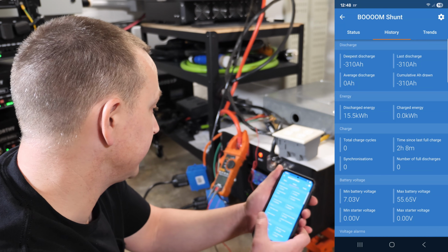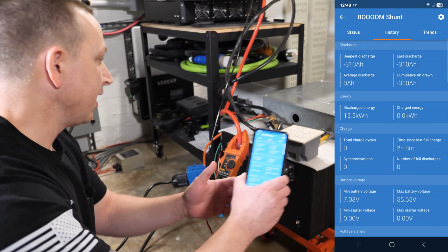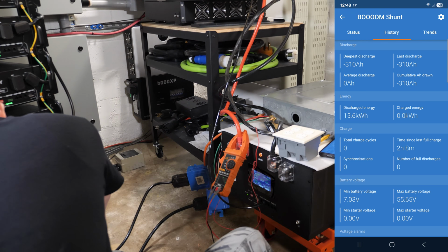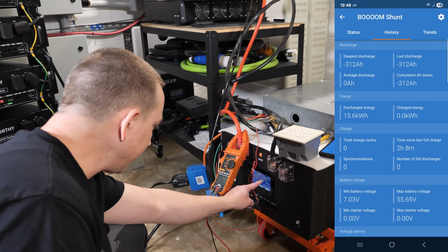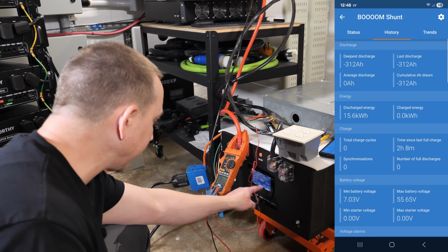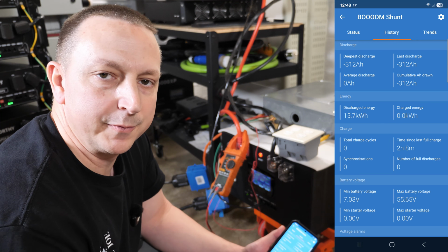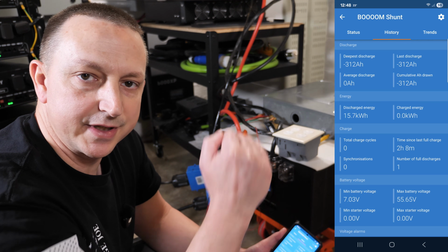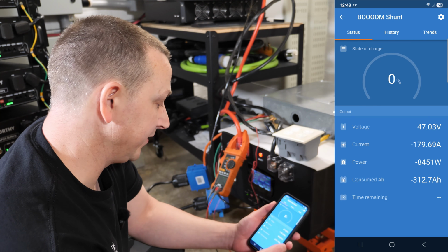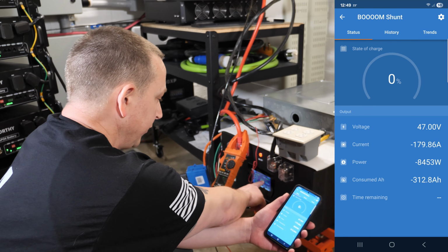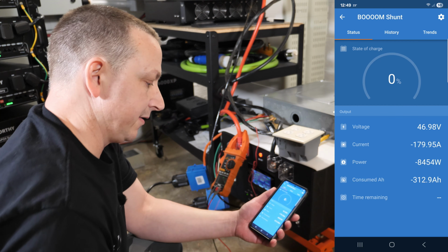I'm going to leave it on here so we can see it. I'm gonna have to adjust the amperage down again. So I dropped it down, we're at 187 right now, and that should give me a little room, because when the voltage goes down the amperage is gonna go up. On here it says we're doing 179.6, over here we're doing 188, which is quite a bit of difference.